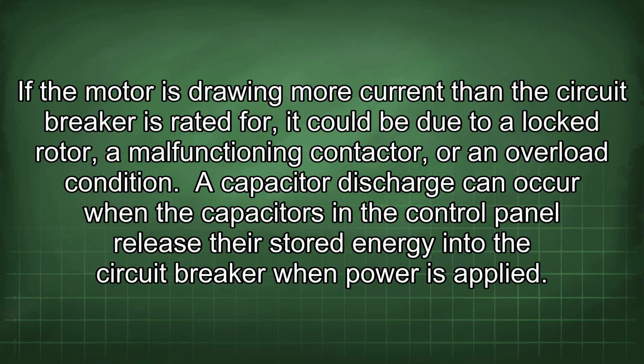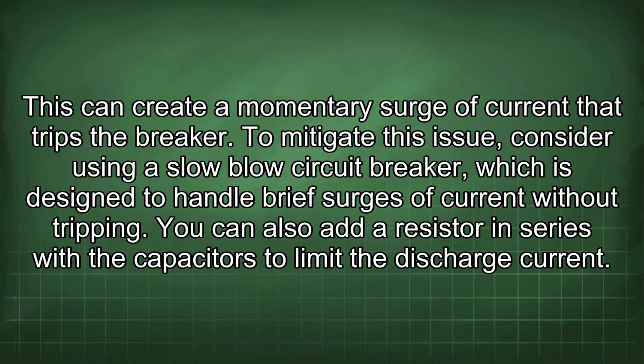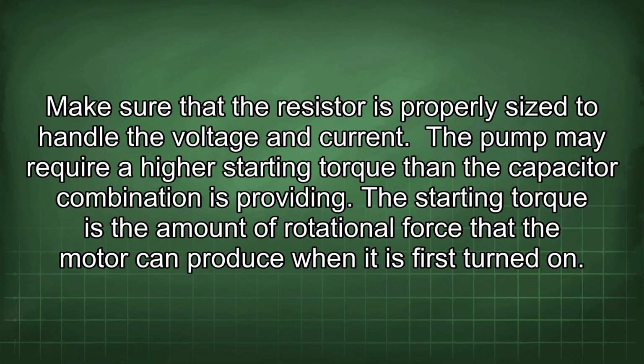A capacitor discharge can occur when the capacitors in a control panel release their stored energy into the circuit breaker when power is applied. This can create a momentary surge of current that trips the breaker. To mitigate this issue, consider using a slow-blow circuit breaker, which is designed to handle brief surges of current without tripping. You can also add a resistor in series with the capacitors to limit the discharge current. Make sure that the resistor is properly sized to handle the voltage and current.